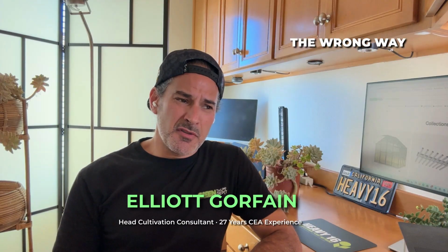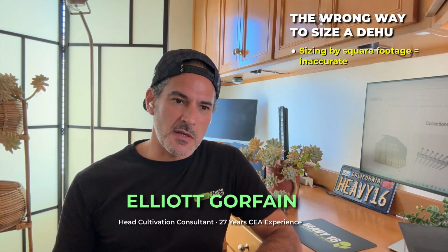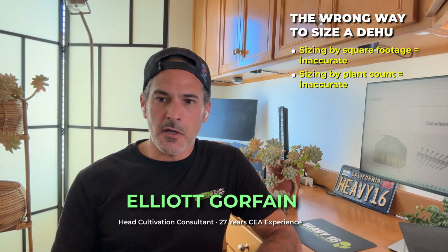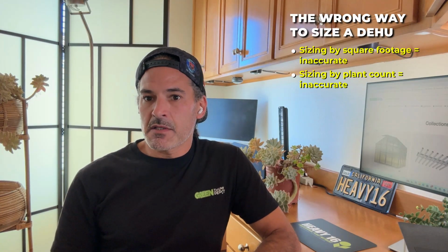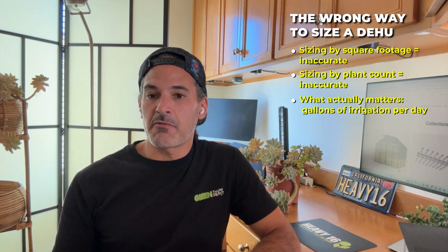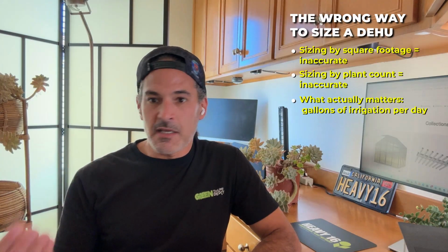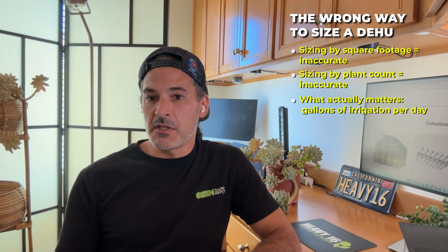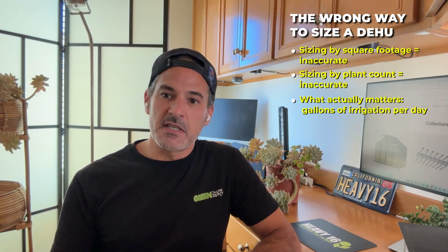Yeah, absolutely. There's a lot of different methods that people use. One of them is estimating it based on square footage. They're estimating it based on the plant count and how big the plants are. Unfortunately, none of these things really matter. What really matters is how much water through irrigation are you putting into that room every day? Because the plants will evapotranspirate approximately 97% of that water. That's really the main figure that you need to know, how much irrigation is going in, because almost all of that water needs to come back out.